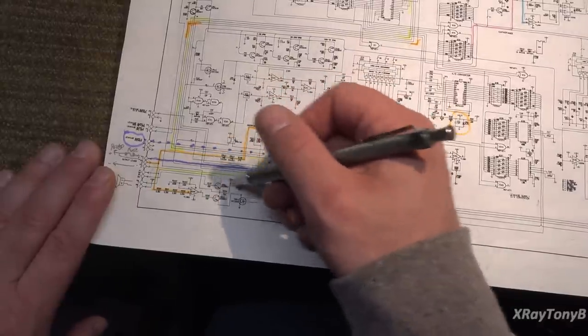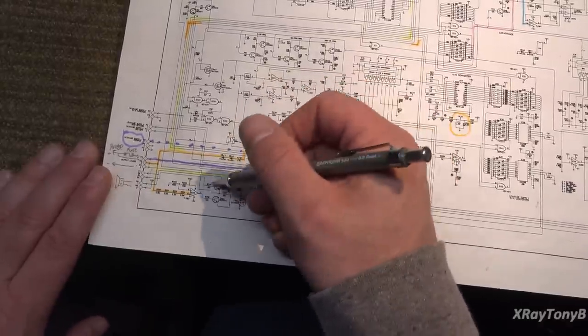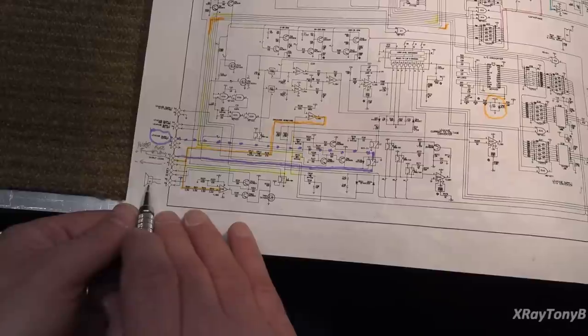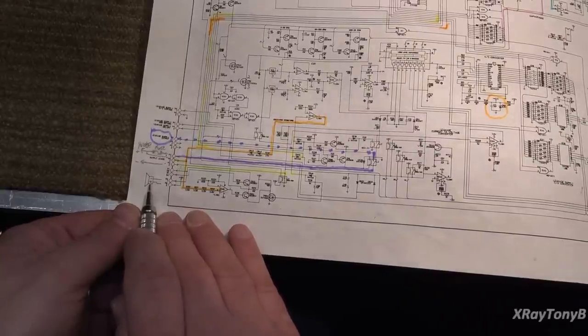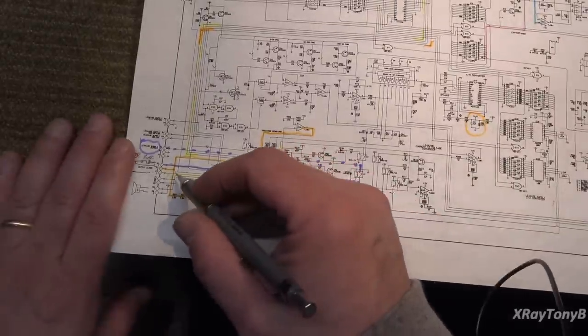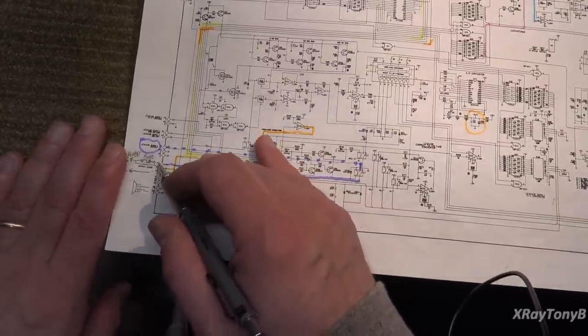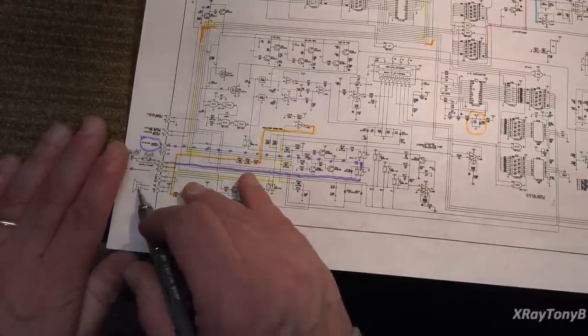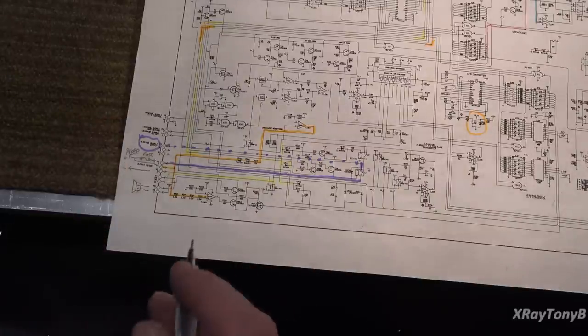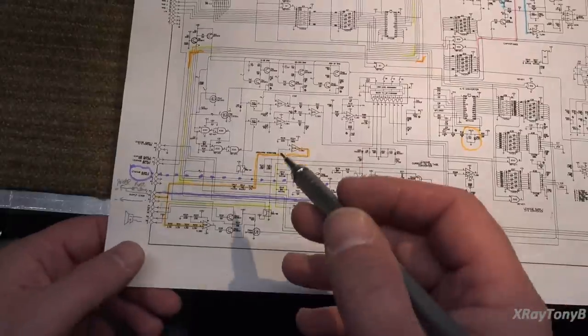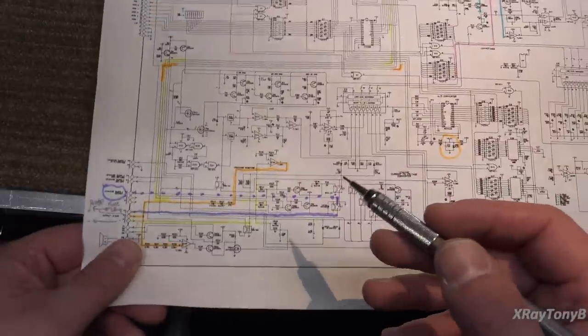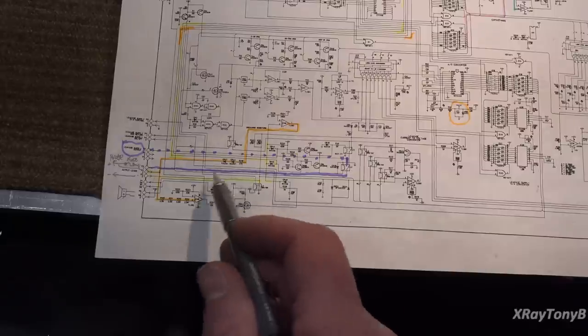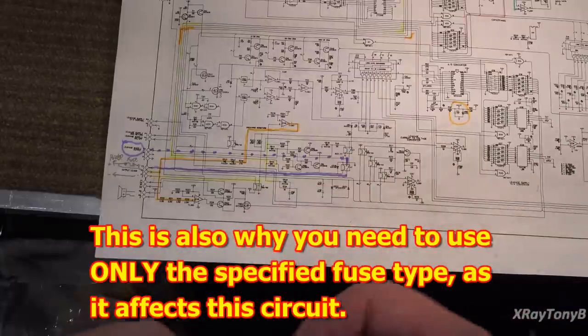So what you have is, you have this little oscillator circuit and so forth. This little circuit in here, and you have this speaker, sonalert, buzzer, on the leakage board. And what happens is, if there's no signal between this fuse and the probe that it can sense through here, it's going to trigger this speaker. And you're going to get that tone and that light will light up that will tell you that the fuse is blown. So that's the open fuse warning. And it also, that tells you, it just kind of protects against that. Or at least, it will let you know that the fuse is open.